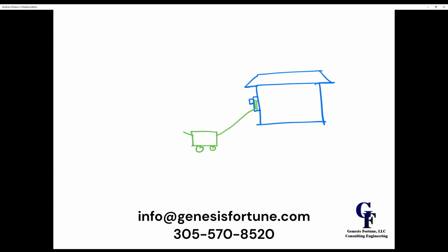These backup generators are usually smaller in size than typical standby generators — there may be big, humongous backup generators, but I'm talking about average size, which is usually smaller than a standby. So here's the generator. What happens is some people who don't know what they're doing, but think they do, forget that while powering the house, you still have power coming from the utility, which has been interrupted — let's say it was interrupted here.